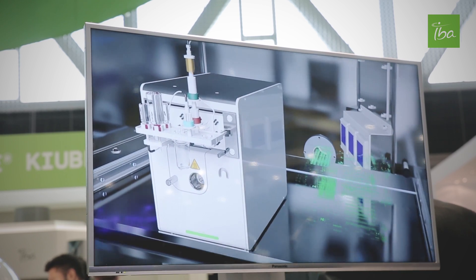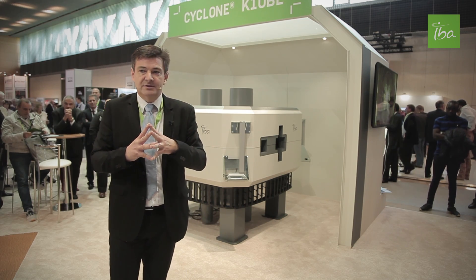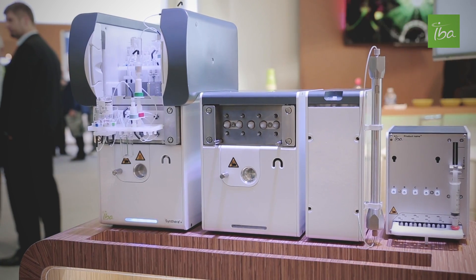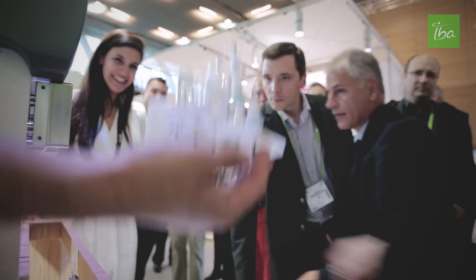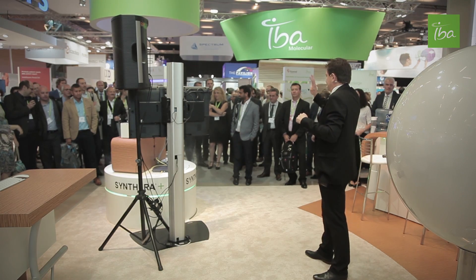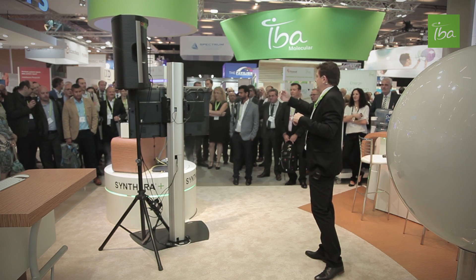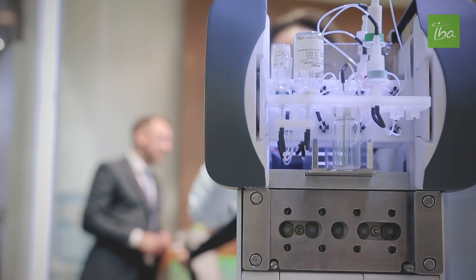I'm now proud to announce the second major breakthrough: the Synthera Plus. Let's unveil the Synthera Plus. What is unique with the Synthera Plus is the loader. On one Synthera, you have up to four IFP cassettes and you have automatic loading and injection, so you can make four batches of various radiotracers without opening the hot cell.